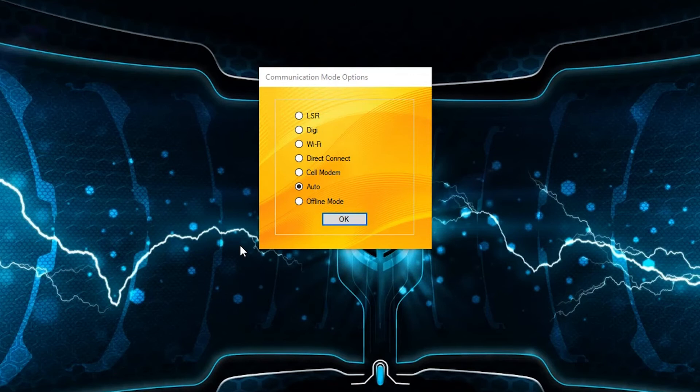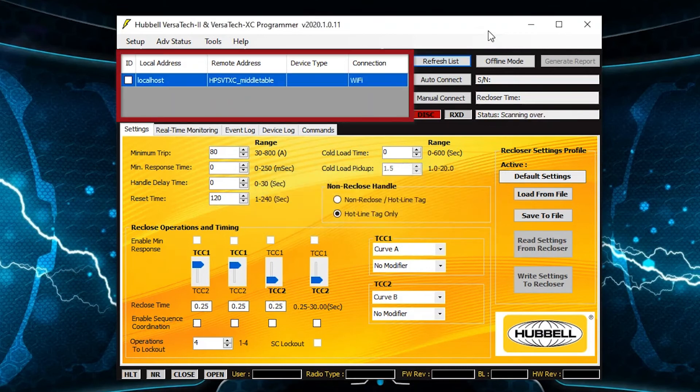Once the local radio is connected to the user's PC and the wireless radio is powered on the VersaTech recloser, the VersaTech connection will be displayed as a COM port in the communications list at the upper left of the UI. As with the serial connection, the COM port needs first to be selected and then identified by clicking on identify device. After identifying the VersaTech, the connect button will be made available for selection to establish communications with the recloser.